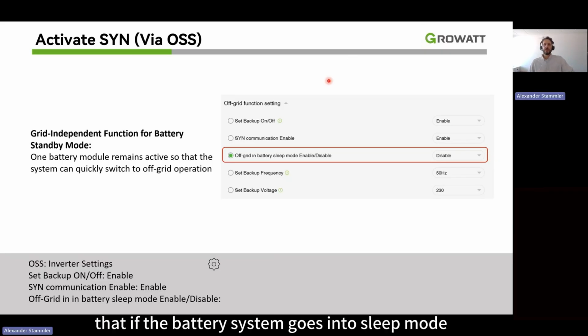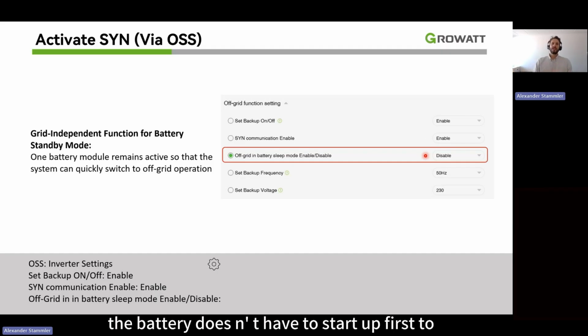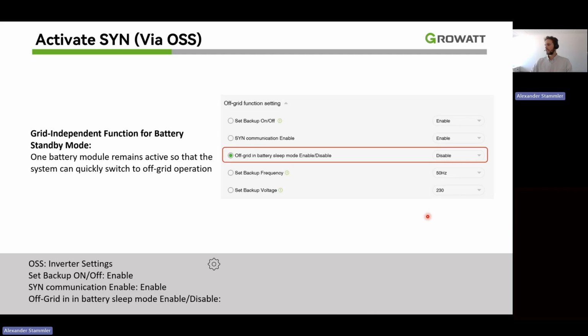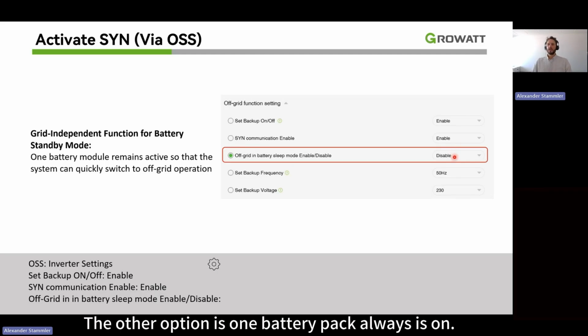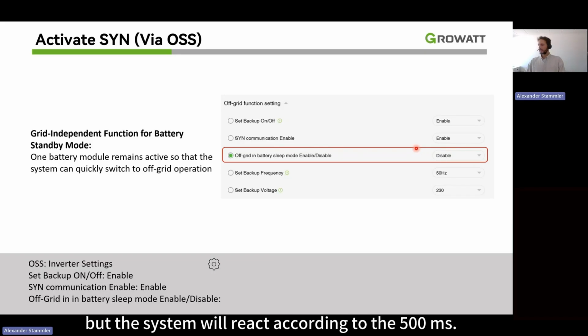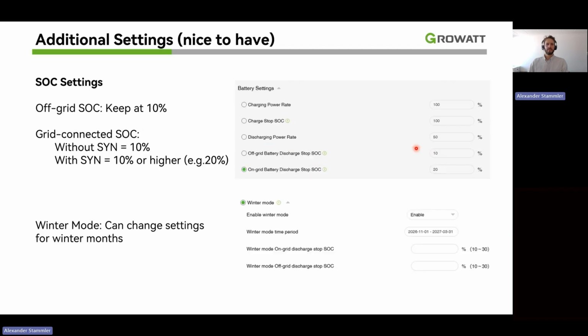for example, that if the battery system goes into sleep mode, you can say that one battery pack stays awake. And this way, when a grid outage comes, the battery doesn't have to start up first to provide power in the night. Otherwise, it first has to wake up. It has to start. It takes a couple of seconds and so. So it will take longer. The other option is one battery pack always is on. This means it will use up some energy, but the system will react within 500 milliseconds.